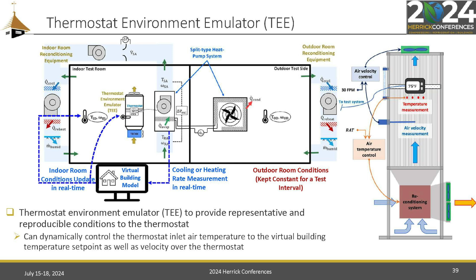One of the things that we found fairly early on is that thermostat placement in the indoor room mattered, and it was really hard to figure out the best way to handle that. And so basically, the Purdue folks that did a lot of this research that was funded by the Northwest Energy Efficiency Alliance and PG&E and some other folks that were involved in this process, they developed a chamber that you put inside that indoor room that is finely tuned to match the control point of the indoor room, and has a consistent air velocity moving across the thermostat sensor or the control.